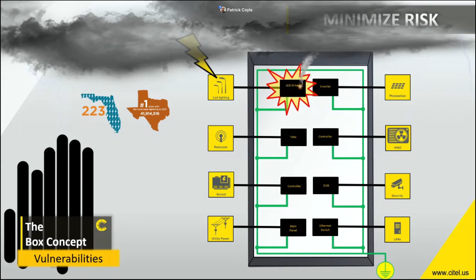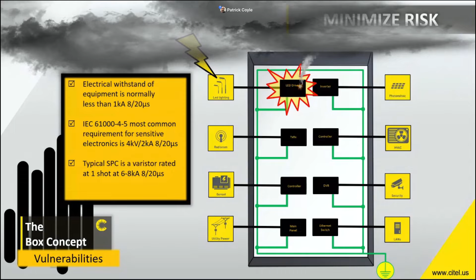So this is pretty much an easy one to understand. No protection, large surge, you got no chance. And why? It's really easy. Most equipment fails at 1,000 amps or less. Most equipment fails with the 4 kV, 2 kA of the ANSI, the IEC 61000-4-5. It's only rated for 4 kV, 2 kA, and then the typical component used is only rated at 6,000 to 8,000 amps. So we had mentioned earlier that the average lightning strike is about 20,000, with the maximum being around 200,000. So here is the not so easy part.